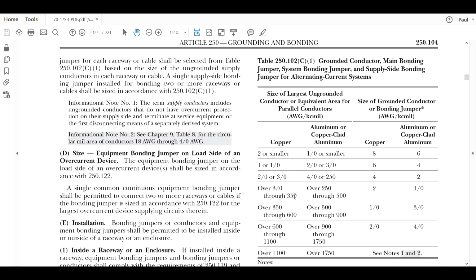In our case, the derived conductors were 350. Now remember here, it says over 3/0 through 350 and then over 350 through 600. I've seen many people on the exam accidentally go here and choose the 1/0. In the real world, it's not going to be a problem because 1/0 is larger than a 2, and that's okay. It's not a code issue. But on an exam, you want the best possible choice. So the best possible choice is right here. It's 3/0 through 350, so it includes 350, and that means it would be a number 2.